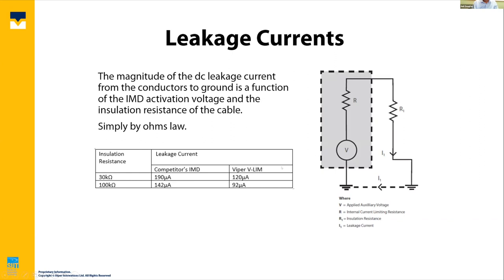If we simplify the umbilical, this is how I really now want you to think about it, where the predominant leakage current is the resistance, the insulation resistance. And when I say it's dominant, if the umbilical is new, it may be capacitance, it may be resistive. However, as the umbilical deteriorates, maybe water ingress, it is the resistive element that predominates the umbilical or the leakage. So from here on in, I'm just going to look at assuming that the leakage current is resistive. And when I talk about insulation resistance, this is really what I'm talking about, this resistance here.